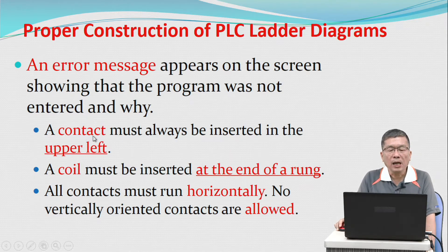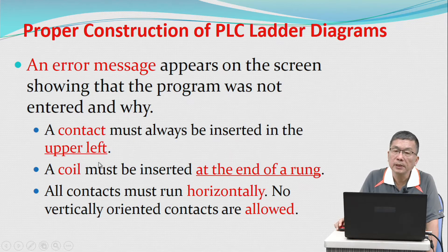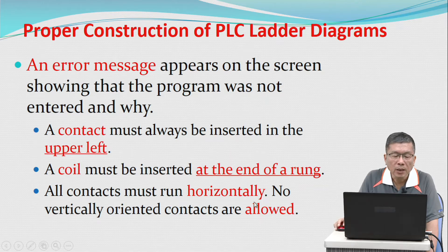A contact must always be inserted in the upper left. A coil must be inserted at the end of the rung. All contacts must run horizontally — no vertically oriented contacts are allowed.